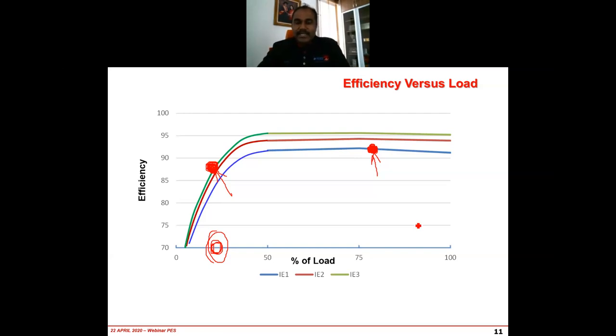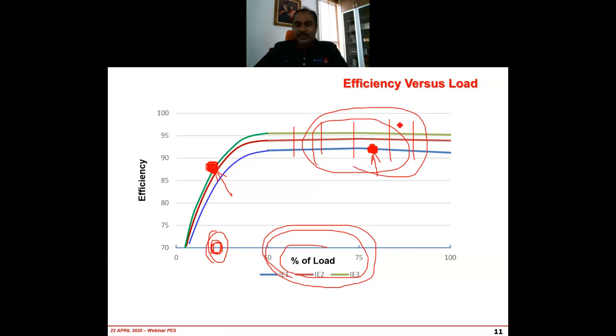So before you even decide whether you want to go for high efficiency motors, the first step is to determine what the loading factor is. Look at where your motor is now. If you're operating in this region, of course you can see that by going for IE2 or IE3 you'll be able to see the saving. But we have seen many cases in industry where the loading is like 50%, 40%. We have seen many. In that kind of system, when you upgrade with the same power value of the motor, you will notice that you're not going to see any savings. That is the big mistake. So what you probably have to do is resize the motor so that it operates at a higher loading condition, and then you think about going for higher efficiency models, right? All right.